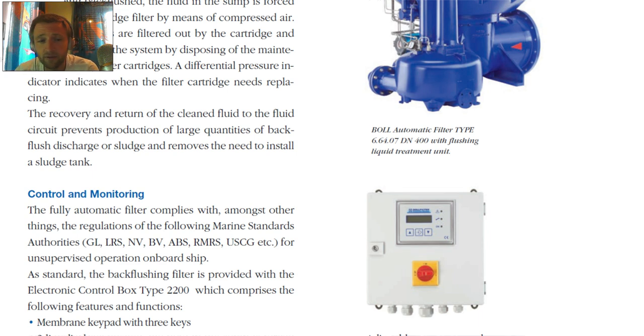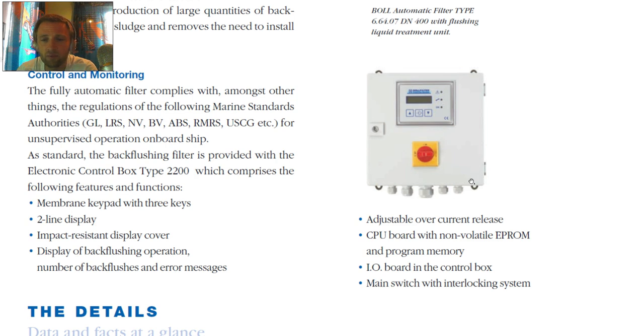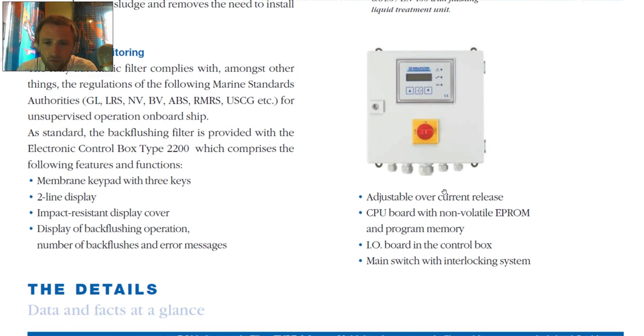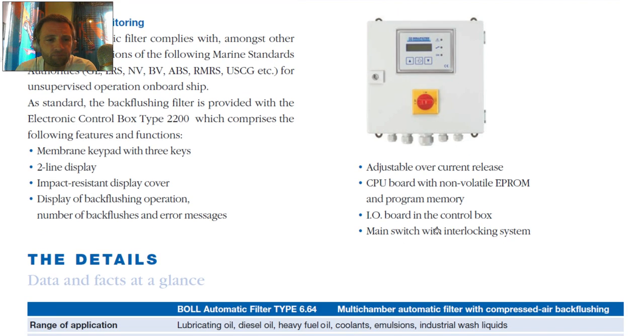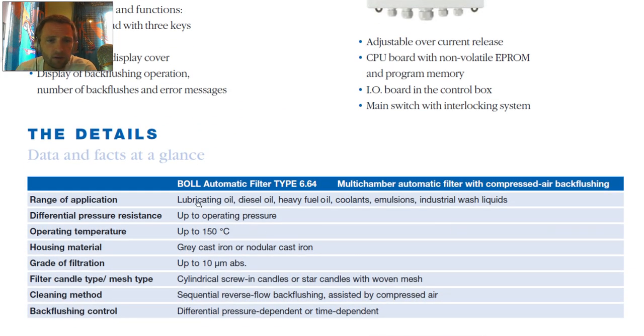The filter is approved by following marine standards. In the control box we can see: adjustable overcurrent release, CPU board with non-volatile EPROM and program memory, I/O board in the control box, and a main switch with interlock system. The operating temperature is 150 degrees, and the grade of filtration is up to 10 micrometers.